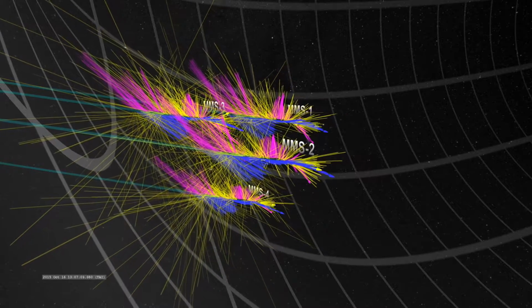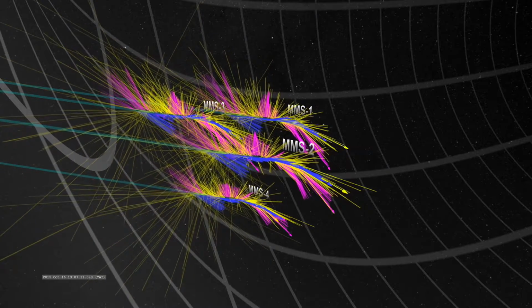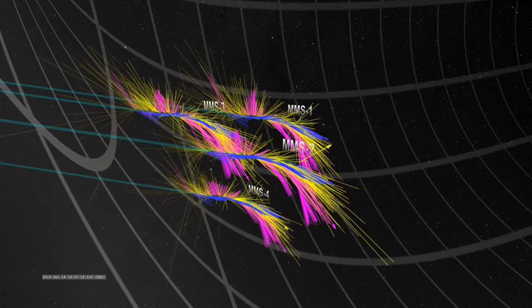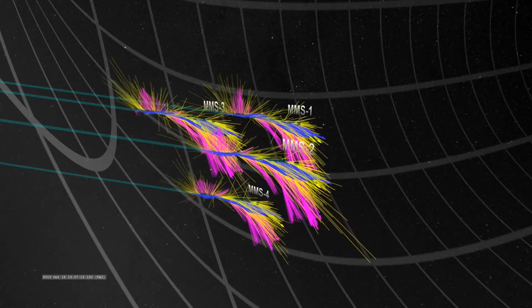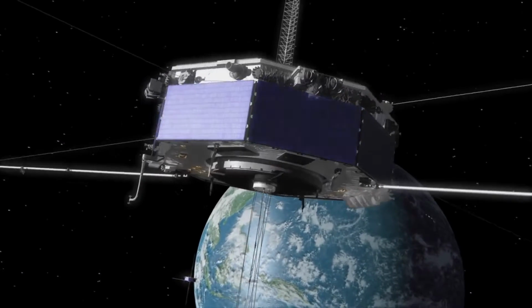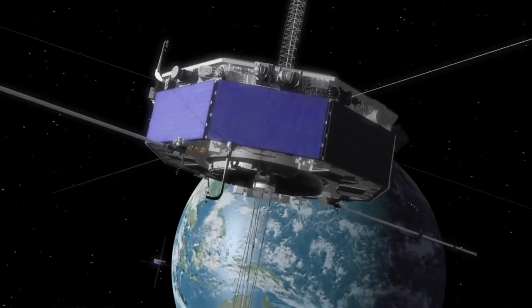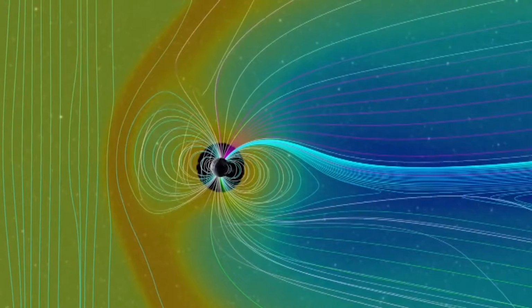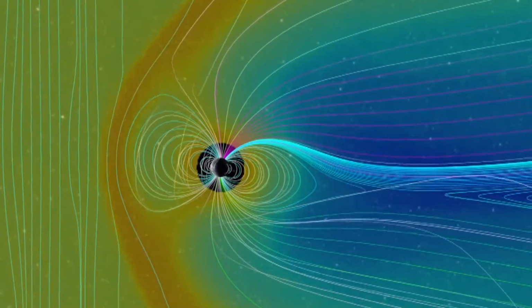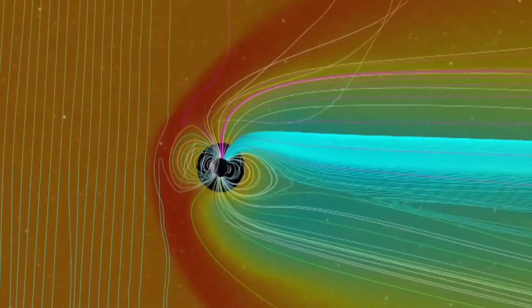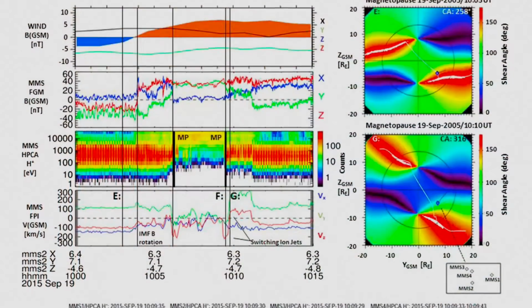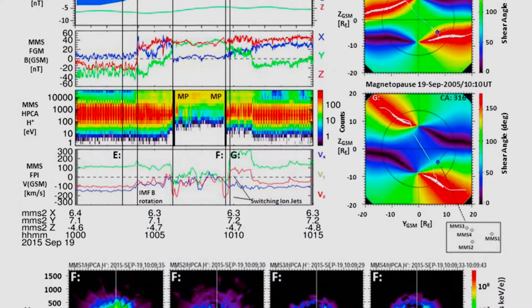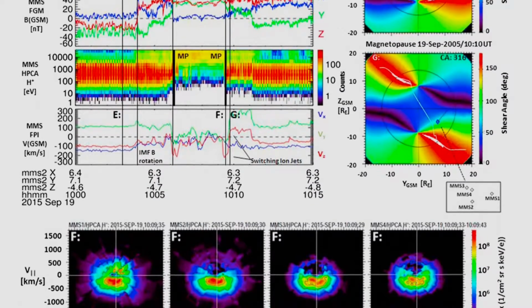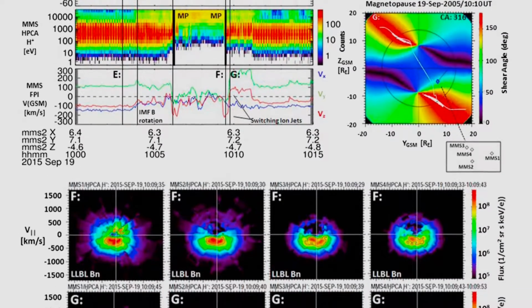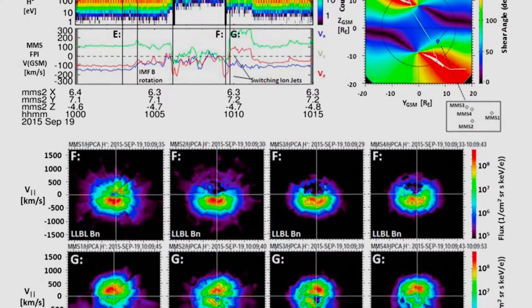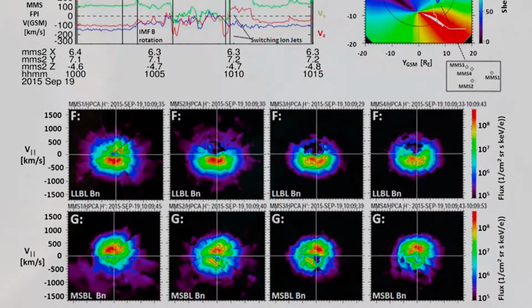On FPI, we need to capture the entire sky in 30 milliseconds, so 100 times faster than any previous mission. So we actually have 32 cameras, if you want to call them cameras, simultaneously capturing data. And we need to stitch all of those together into one set of images. And that's the hardest part of this calibration, is making sure when you put all these things together, there's no discontinuity, there's no offset. Everything looks perfectly smooth when you look at the data at the end of the day.